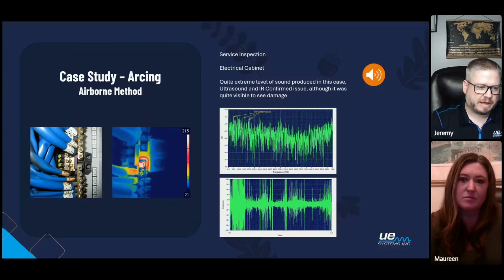Okay. So we hear it, and at first glance, it almost sounds like somebody's just scooting along and maybe rubbing something there. But actually, at that discharge, the signature displayed it. It was classic arcing. And if we have arcing, we don't consider it something we measure and say, well, let's see how bad it is in a month or in a couple of weeks. We want to take immediate action on that.